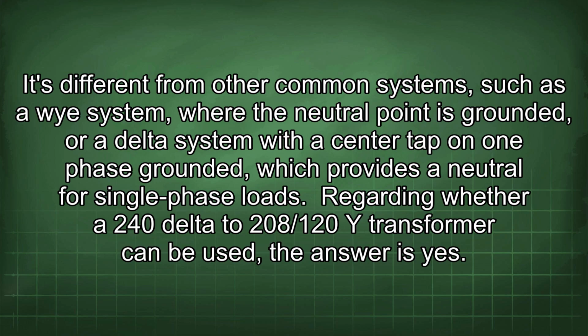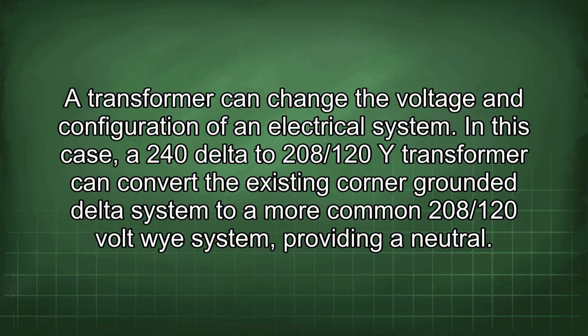Regarding whether a 240 delta to 208/120Y transformer can be used, the answer is yes. A transformer can change the voltage and configuration of an electrical system. In this case, a 240 delta to 208/120Y transformer can convert the existing corner grounded delta system to a more common 208/120 volt Y system, providing a neutral.